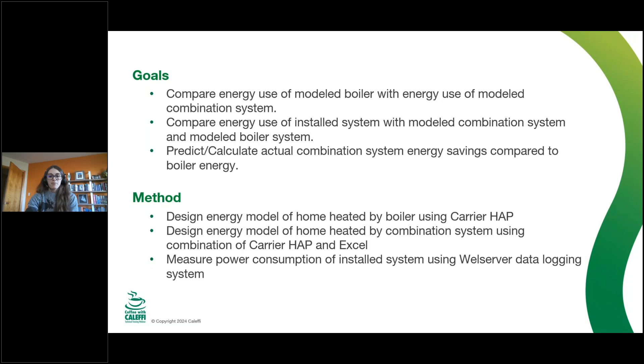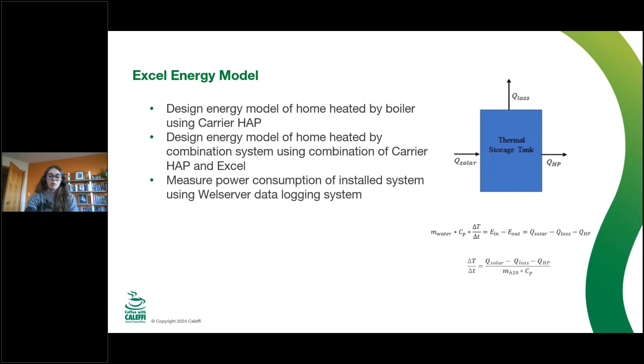I'll breeze through some of this to get to the good part—the results. This is an example of the heat balance I did on the thermal storage tank to create the Excel energy model. I used the hourly home loads from HAP as input for that Excel program, then calculated the hourly input and output of the thermal storage tank and the open loop ground source heat pump.